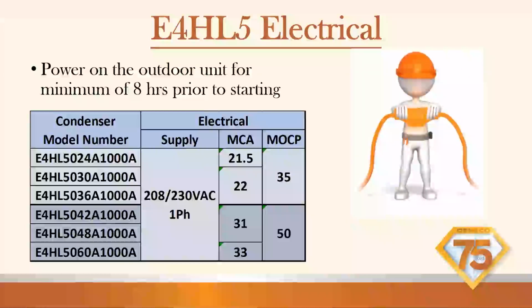So there's an algorithm in there that preheats the winding. So I recommend as soon as you're doing a retrofit, get that outdoor unit energized, no control wires, but get it energized, get that preheating of the compressor started. I like Jonathan's terminology of the compressor. If you put your hand in your armpit, the compressor should be that warm before you start it. So keep that in mind. The compressor should be about armpit temperature before you start it.